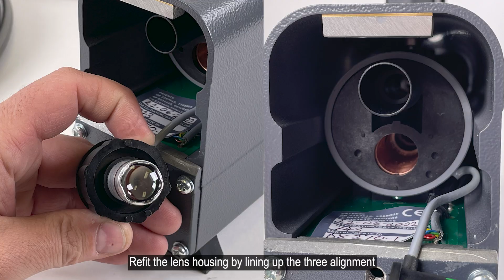Refit the lens housing by lining up the 3 alignment pins with the corresponding holes in the sampling tube. The lens is refitted correctly when it cannot be rotated. Refit the end cap and tighten the knurled knob. Repeat these steps on the other end of the smoke head.